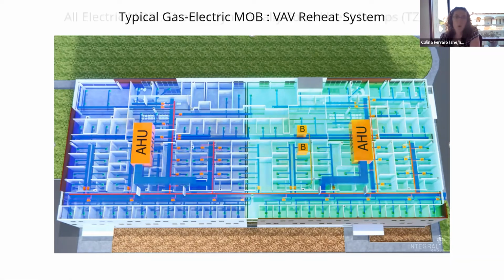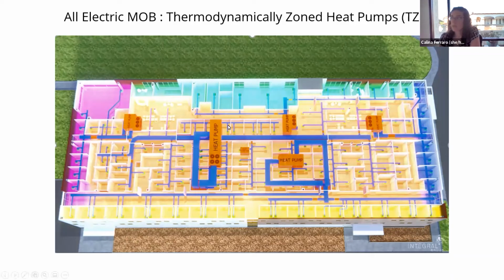What it looks like instead with our thermodynamically zoned system is much smaller heat pumps for these smaller zones. We do still have one large heat pump that does that central zone, but around the perimeter, you can see we have much smaller ductwork serving those zones. All of the heating and cooling gets done by the compressors at the unit. So it's an all-electric strategy, and it allows us to completely eliminate those hydronic boilers and all of that heating hot water piping. That was how we were able to get rid of the gas from the mechanical side for building heating, by using these heat pump technologies, because we have to do the cooling anyway. That same compressor can flip a reversing valve and supply hot air instead, because we don't need to do both at the zone. We just do one or the other up at the unit. So we were able to get the gas out of the mechanical system.